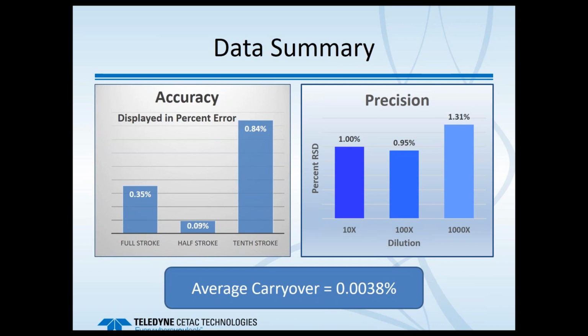And then we also did a carryover study where we prepared a 100 ppm standard at a 1 to 10 dilution directly. After that, we prepared a blank solution also at a 1 to 10 dilution. And then those were run on the ICP, the blank not directly following, but following a separate blank so we could get appropriate readback on any sort of carryover in the auto diluter. And the average carryover came out to be 0.0038%, that you see there, which we were very, very pleased with.